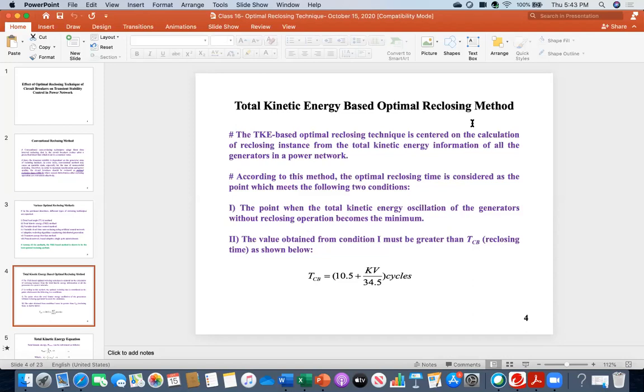And once you get that total kinetic energy information, you have to apply some technique. That technique will tell you whether this is the optimal reclosing instance or not during a fault. So what is that method? This is the method. Everybody see that second line. According to this method, the total kinetic energy based method, the optimal reclosing time is considered as the point which meets the following two conditions. Now there are two conditions, number 1, number 2.